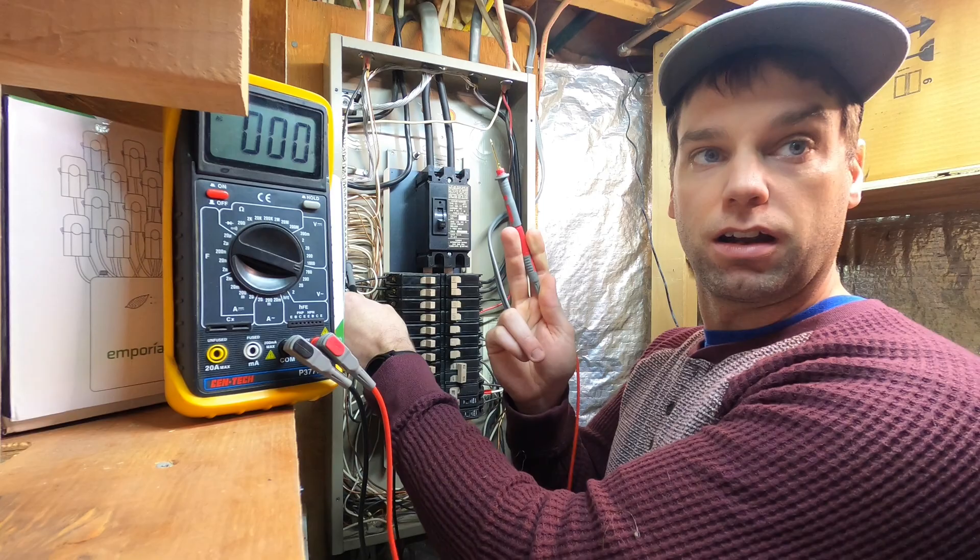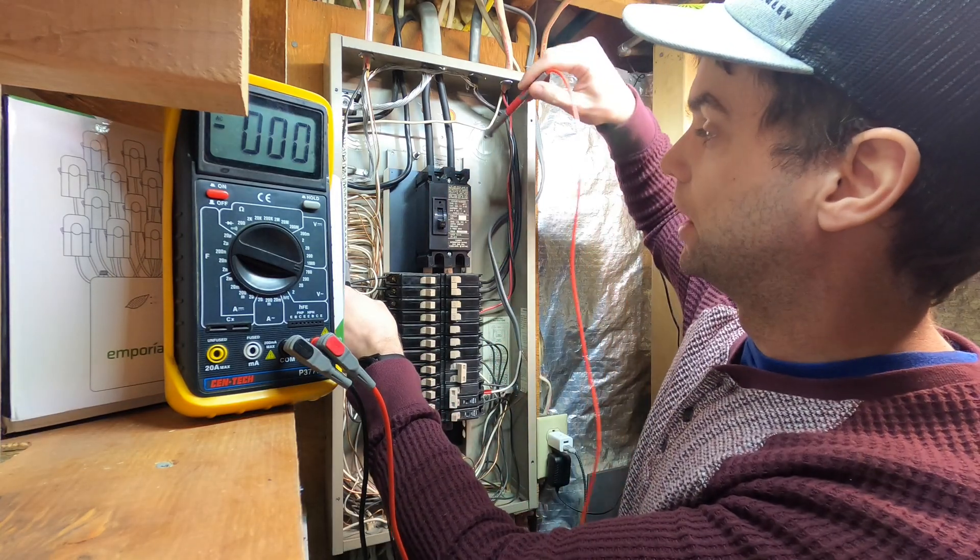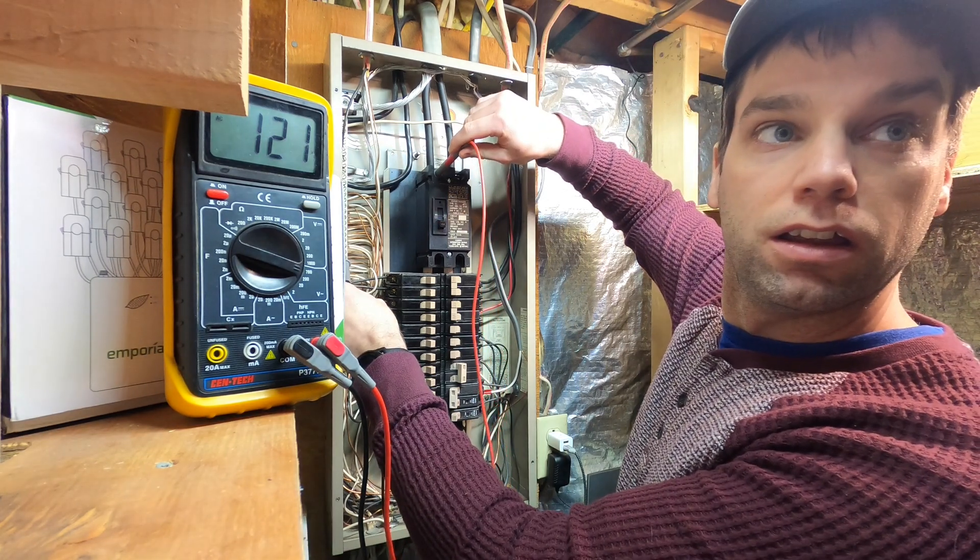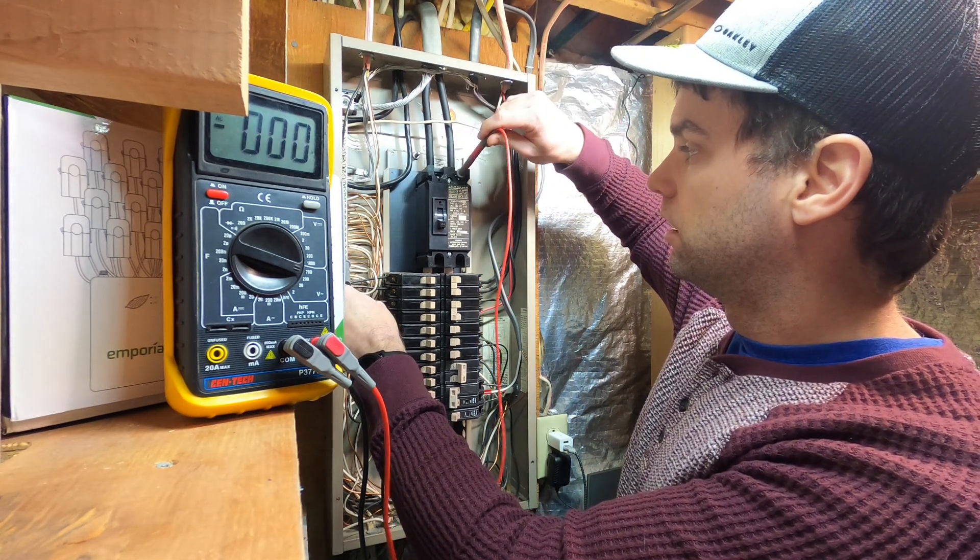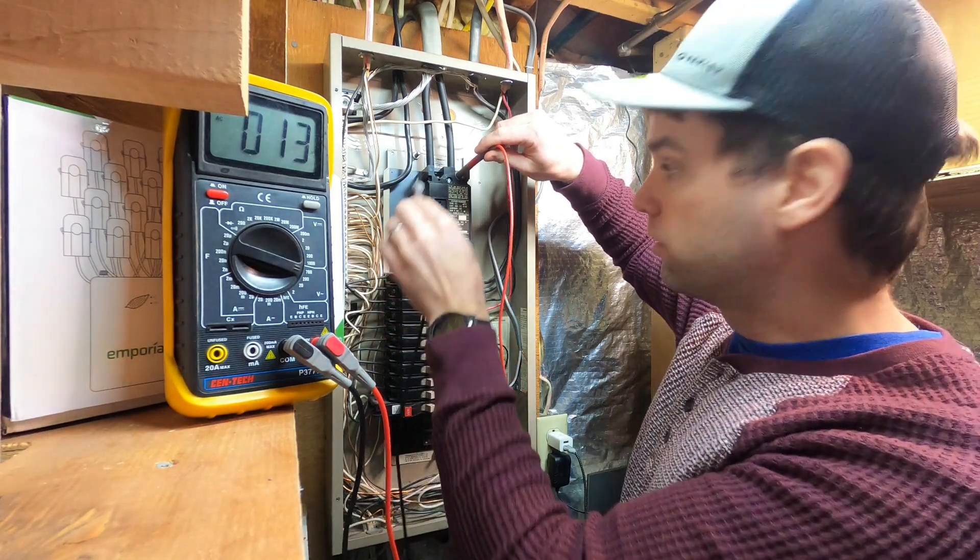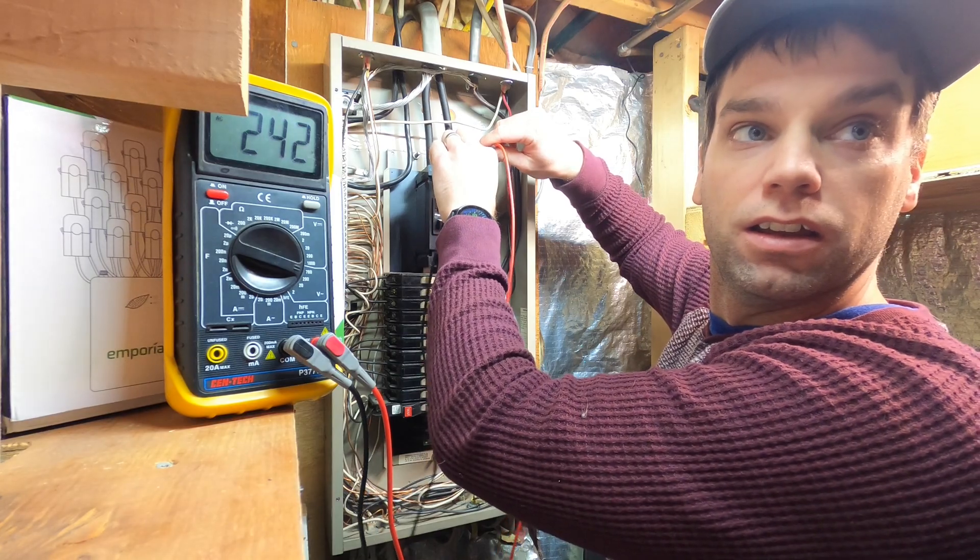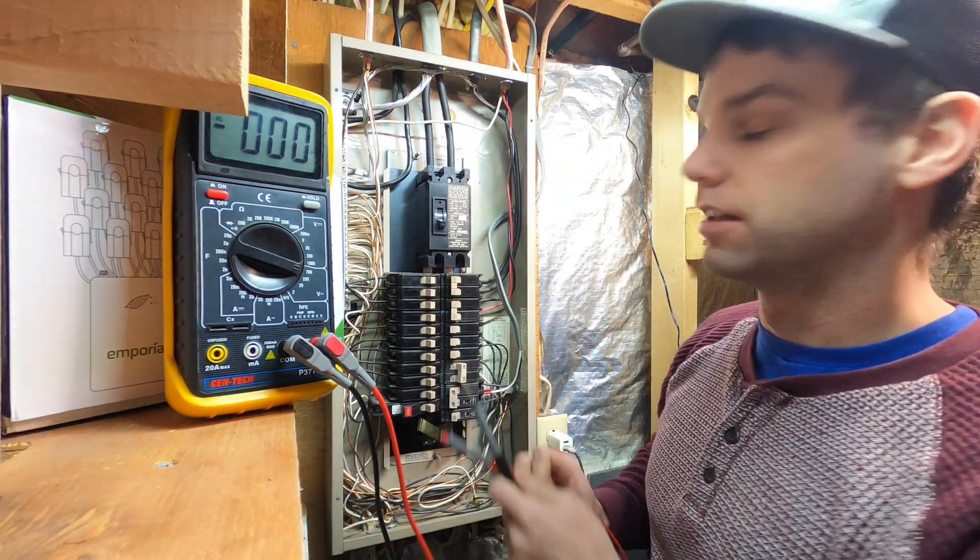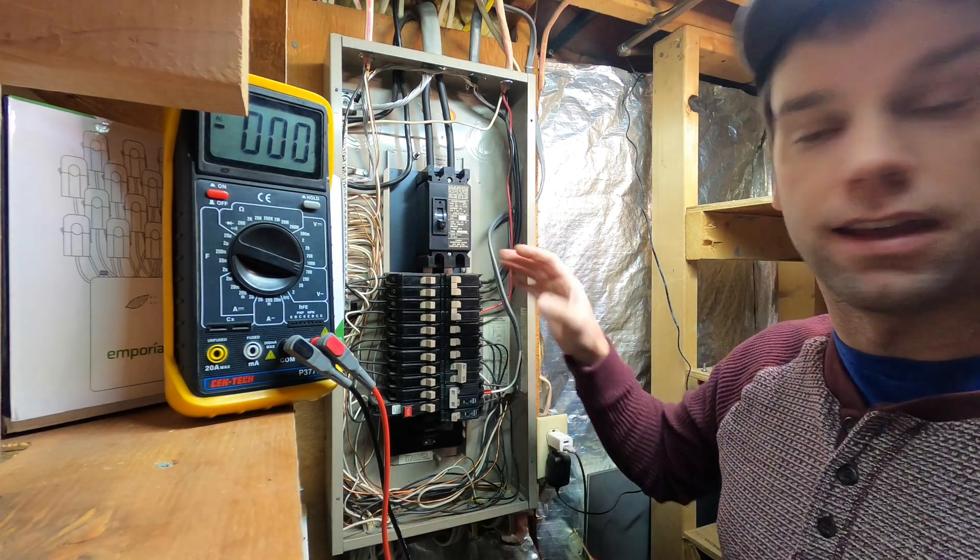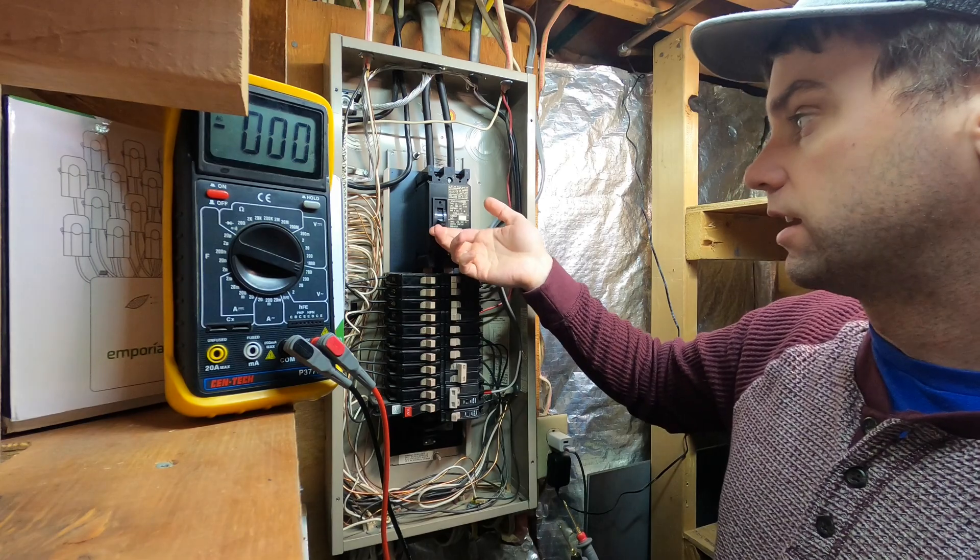But then we're going to take our red hot lead and we're going to be very careful not to touch anything inside of here and check on our main breaker. And you can see we've got 120 volts there on the left leg and 120 volts on the right leg. And if we take our negative and check it across both legs, you can see we have our 240 volts. So this is still live.